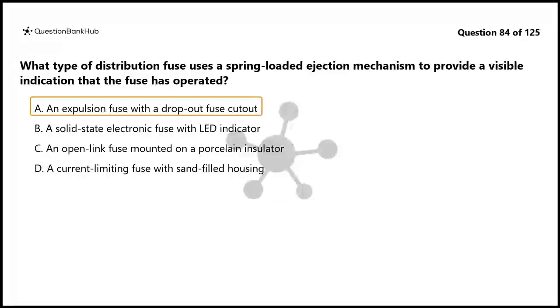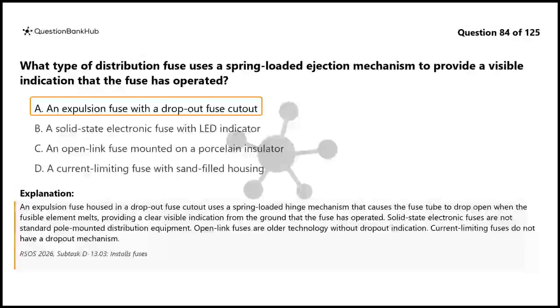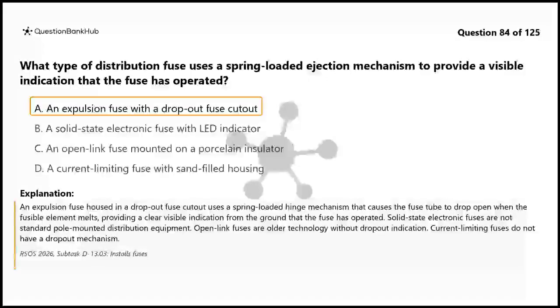The correct answer is A. An expulsion fuse housed in a dropout fuse cutout uses a spring-loaded hinge mechanism that causes the fuse tube to drop open when the fusible element melts, providing a clear visible indication from the ground that the fuse has operated. Solid-state electronic fuses are not standard pole-mounted distribution equipment. Open-link fuses are older technology without dropout indication. Current-limiting fuses do not have a dropout mechanism.